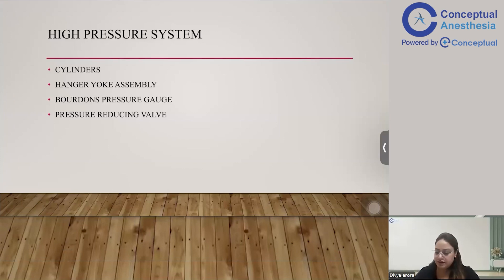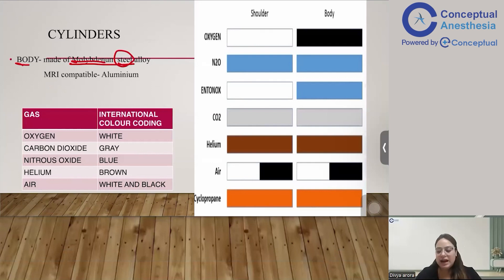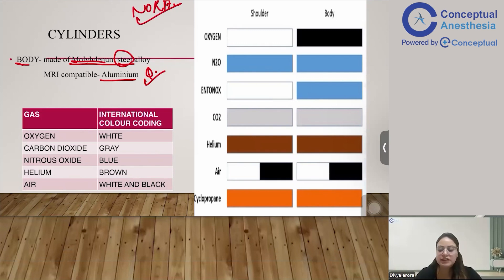Starting with the cylinders in the high pressure system: the cylinder body is made up of molybdenum steel alloy. With newer developments, carbon-molybdenum steel alloy mixtures are also used. Importantly, MRI-compatible cylinders can be taken inside the MRI room — these are made up of aluminium. This is a common MCQ point for DNB, final year MD, viva exams, and for NORA cases as well.